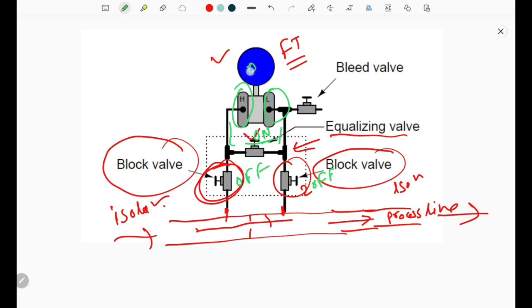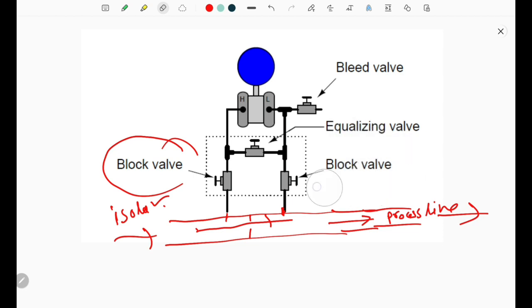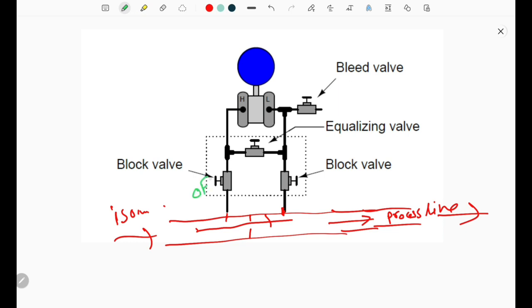When equal pressure is applied on both sides, the transmitter will show a zero value. This is the function of the equalizing valve. Alternatively, we can close both block valves, open the equalizing valve, and when the process equalizes the pressure on both sides, at that time also our transmitter will show a zero value.